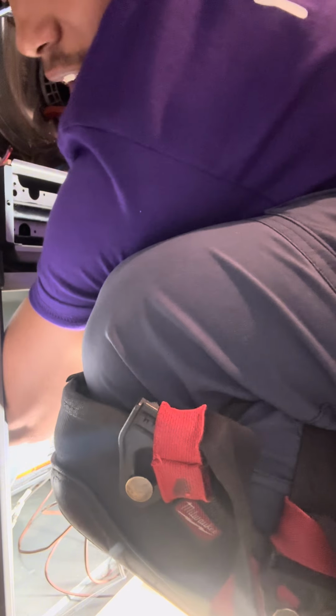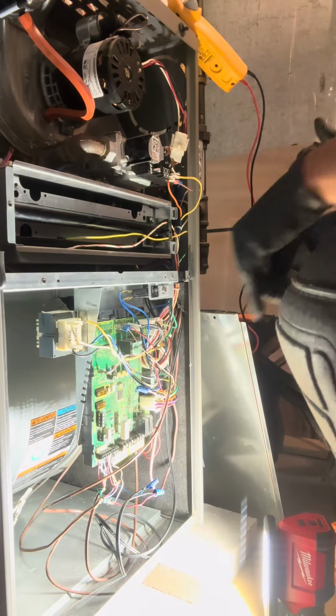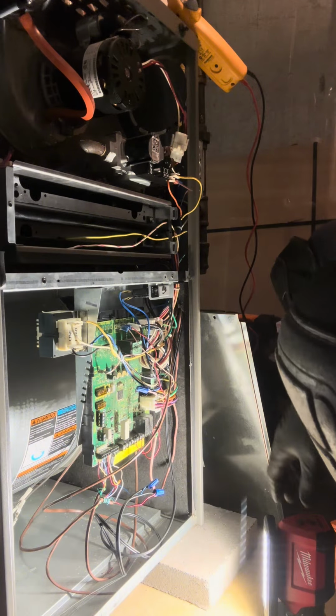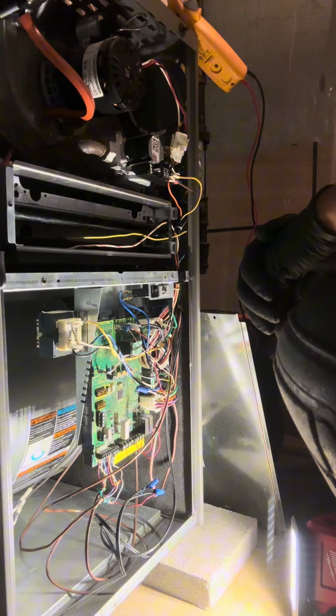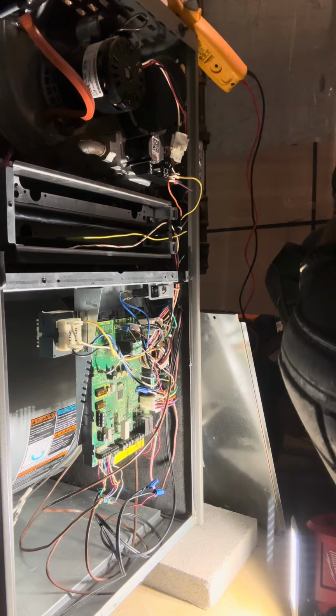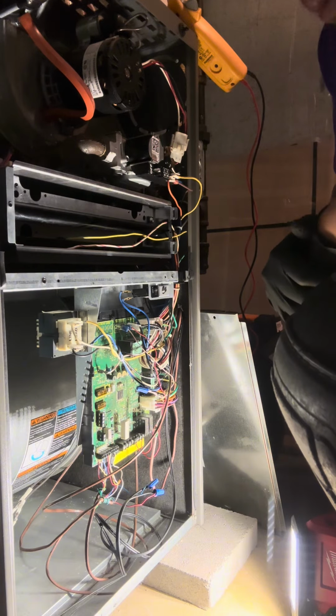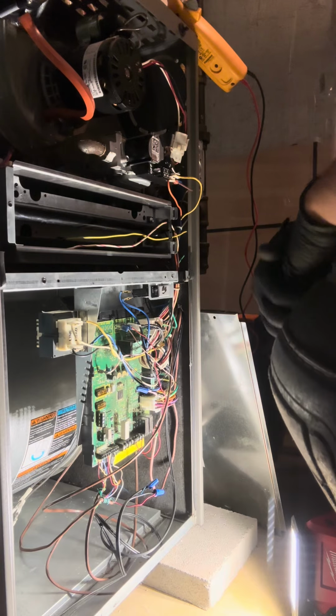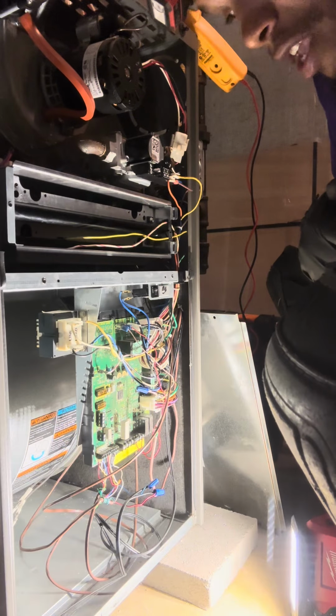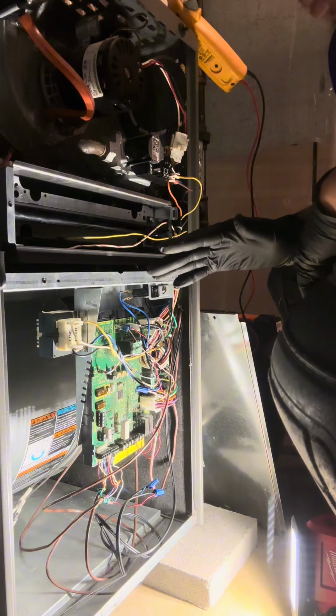I'm also going to reach my hand in and grab the shaft of the blower wheel and just try to wiggle it, see if it wiggles back and forth or forwards and backwards. And I have no wiggle on this blower, so that lets me know that that blower is in pretty good shape. All right, and as far as your blower compartment, those are the main things you need to do. That's an ECM motor, which is an electronically commutated motor, which means that this blower wheel does not use an external capacitor. Everything is built into the blower's module.